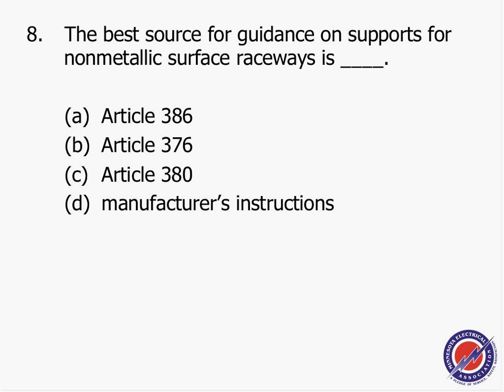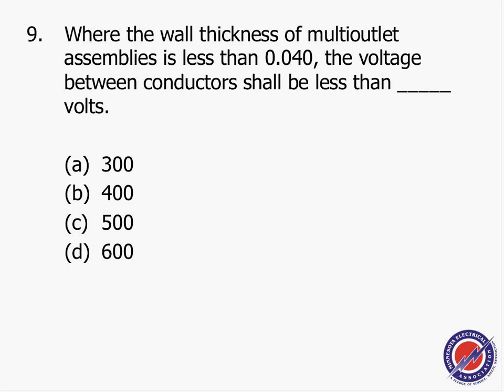Number 8, guys, the source for guidance on support for non-metallic raceways is, again, don't get confused, the manufacturer's instruction. These are not wireways, these are raceways. You have to go by the manufacturer's instruction for support, and I told you guys, remember, I said that.